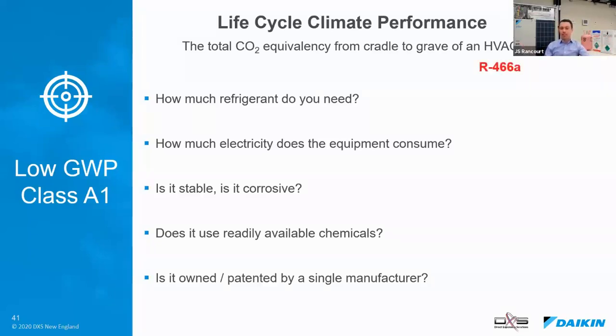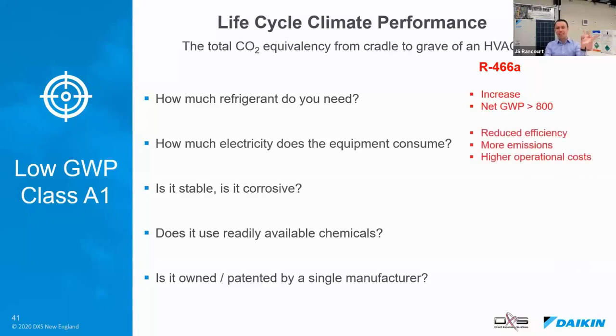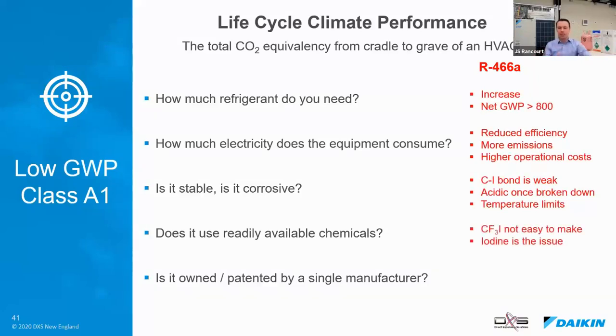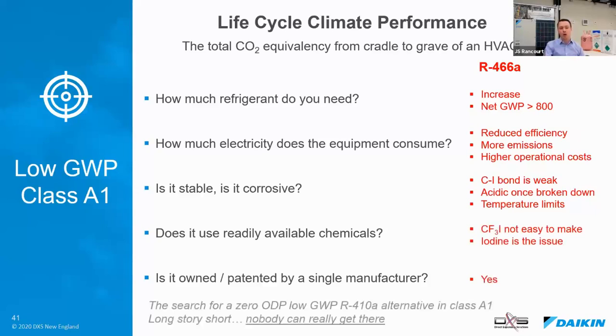So again, I'm going to pick on R466A, mainly because I don't think this was ever going to be a viable refrigerant, so I can pick on it. Here's an example of one that seems like it's got it, A1, low GWP, but you need a lot more of it. It's less efficient, with more emissions and more operational costs. It has stability issues, and it needs additives, and then there are temperature limits, and that iodine molecule in there is an issue. It's expensive to make, and it's owned by one company under a patent. So that's why you have to be careful. And to date, there's essentially no A1 refrigerant that can beat R410A by a lot in terms of GWP.